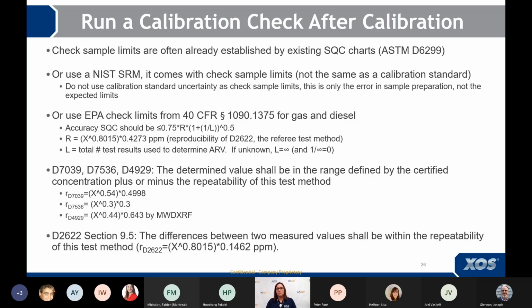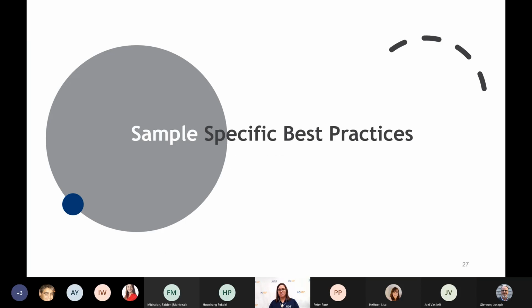This is especially handy when you have a new analyzer and you don't have a control chart set up yet. And of course, if you look in 2622, there's a similar statement, although it says that the differences between two measured values shall be within the repeatability of the test method. Okay, that's the section on calibration.